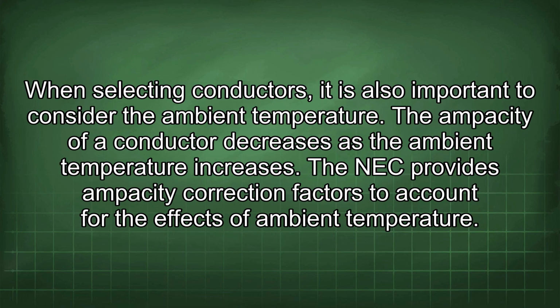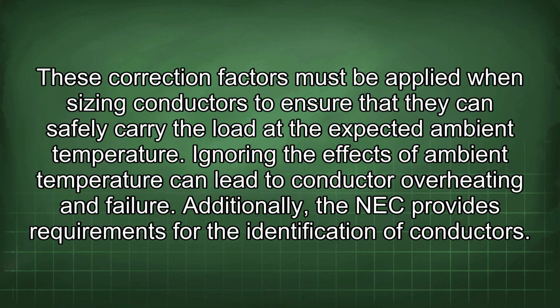When selecting conductors, it is also important to consider the ambient temperature. The ampacity of a conductor decreases as the ambient temperature increases. The NEC provides ampacity correction factors to account for the effects of ambient temperature. These correction factors must be applied when sizing conductors to ensure that they can safely carry the load at the expected ambient temperature. Ignoring the effects of ambient temperature can lead to conductor overheating and failure.